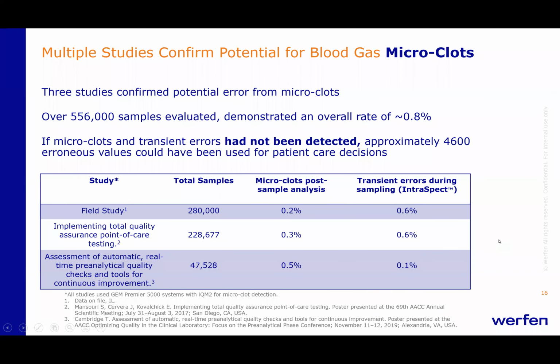There were 3 studies done in various hospitals throughout the world with various operators, and they came up with very similar results from microclots. Microclots post-analysis range from 0.2 to 0.5%, and transient errors, where it's picked up only with IntraSpect, that's during the sample analysis, range from 0.1 to 0.6%. So the overall rate on these 550,000 plus samples was about 0.8%. If you look at the gross numbers, that would mean there would have been 4,600 samples reported with erroneous values if they had not been detected due to the presence of microclots.